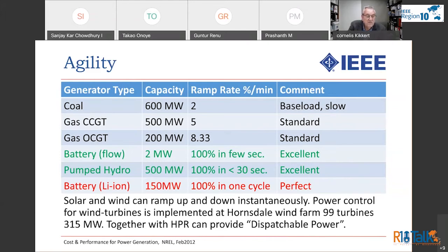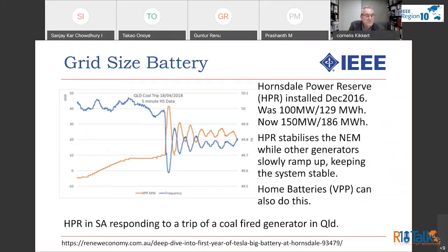The Hornsdale wind farm has got 99 turbines of 315 megawatt, and together with the South Australia's big battery will then provide dispatchable power, and that uses the principle of running the wind farm below the maximum power output. The Hornsdale Power Reserve was a 100 megawatt battery, the biggest battery in the world. It's now 150 megawatt, and you can see that's responding there to a trip of a coal-fired power station in Queensland, and does that perfectly. Home batteries can also do that.